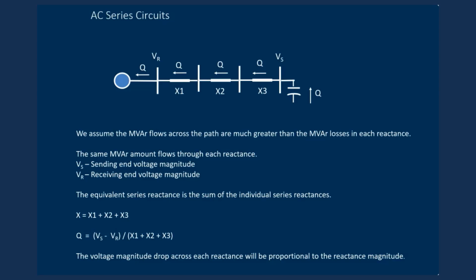Let's look at a simple AC series circuit where we have a single generator regulating its receiving bus, and we have a single shunt capacitor producing megavars Q into a sending bus, and that reactive power is being transmitted over this set of transmission lines, each with reactances X1, X2, and X3, all in series. We will ignore the megavar losses in each reactance, as well as the shunt capacitance of the transmission lines for this simple analysis.